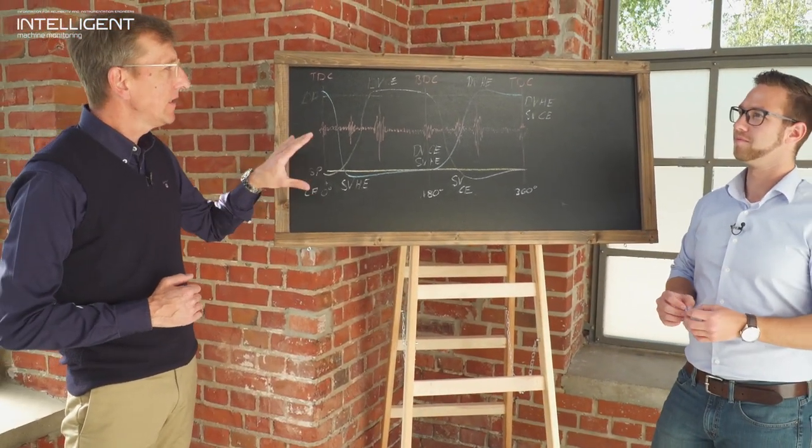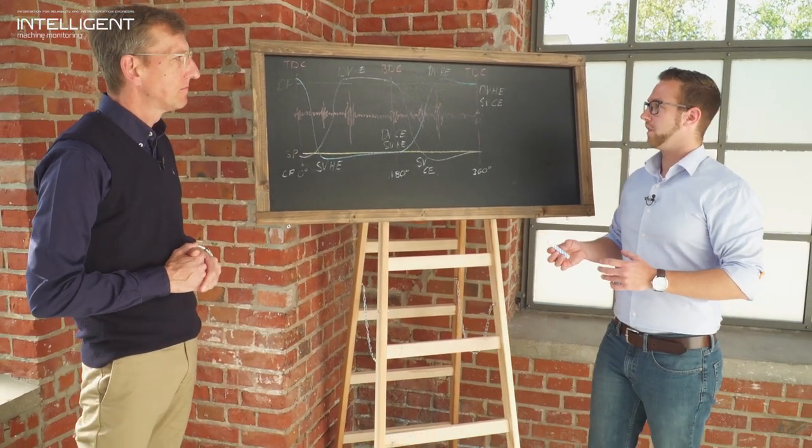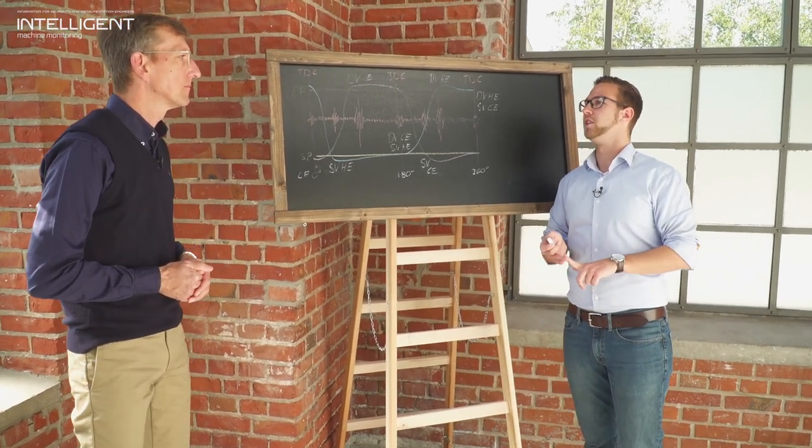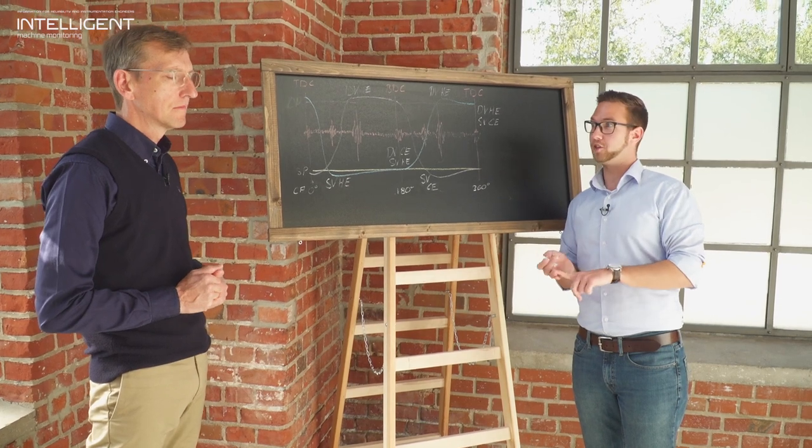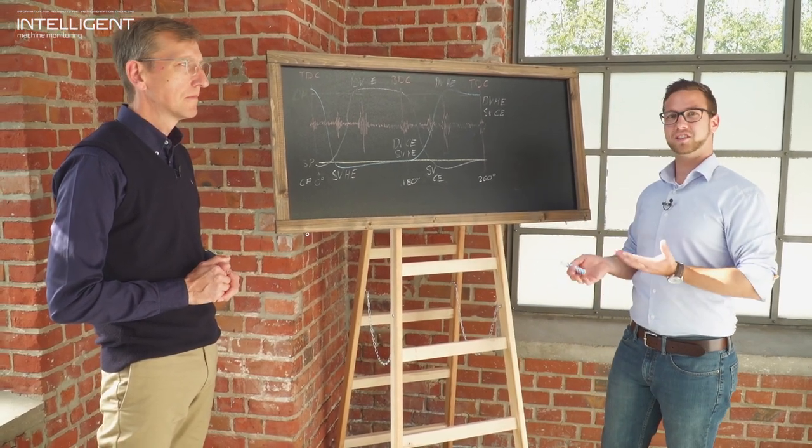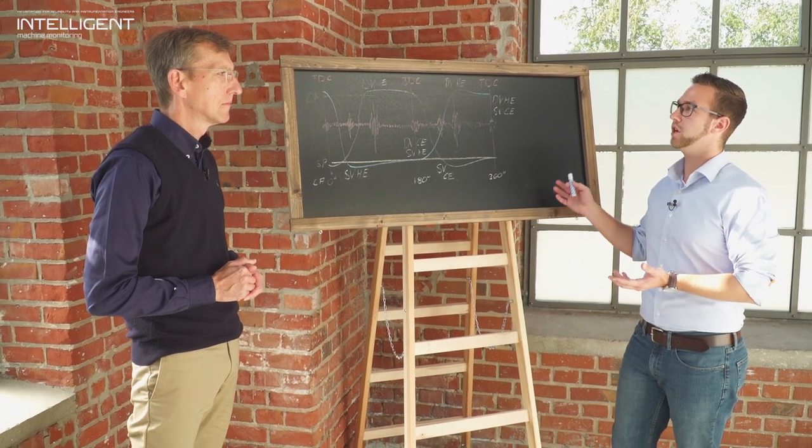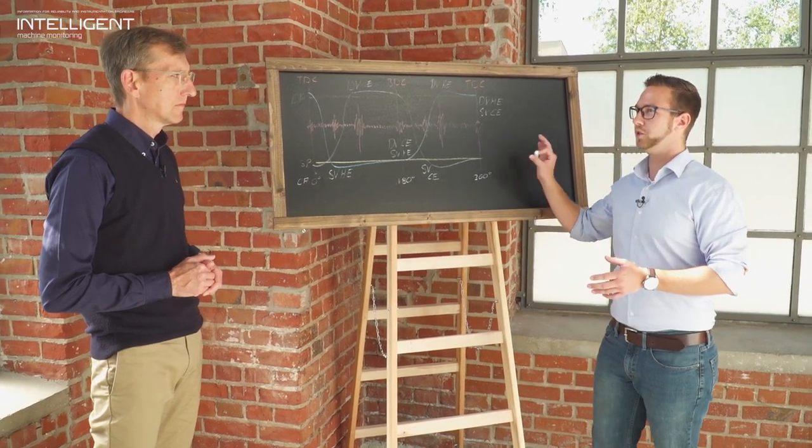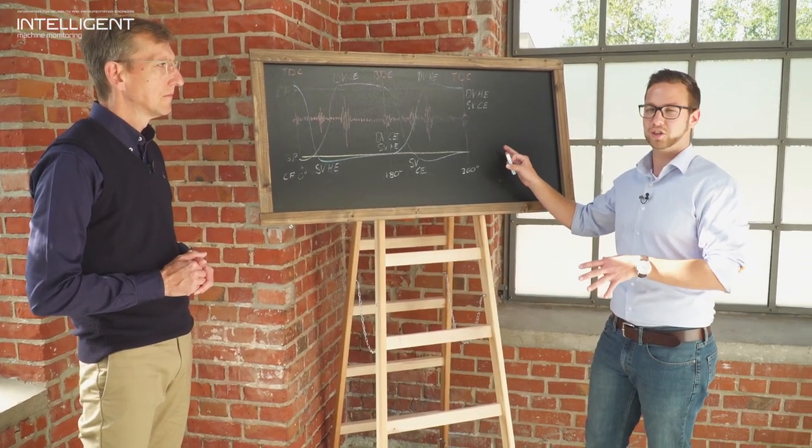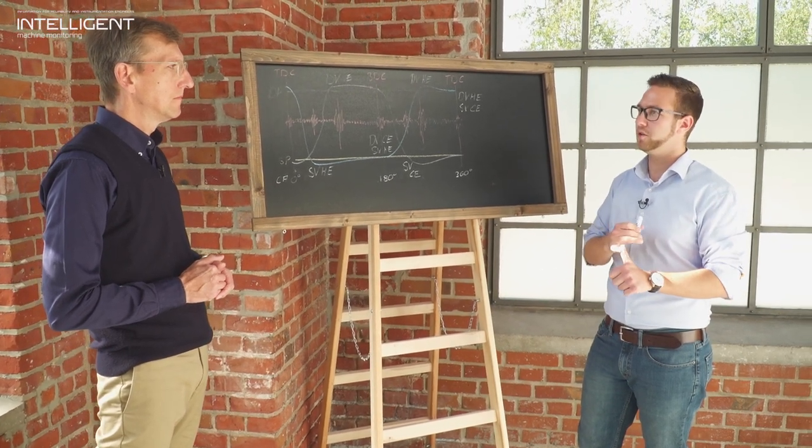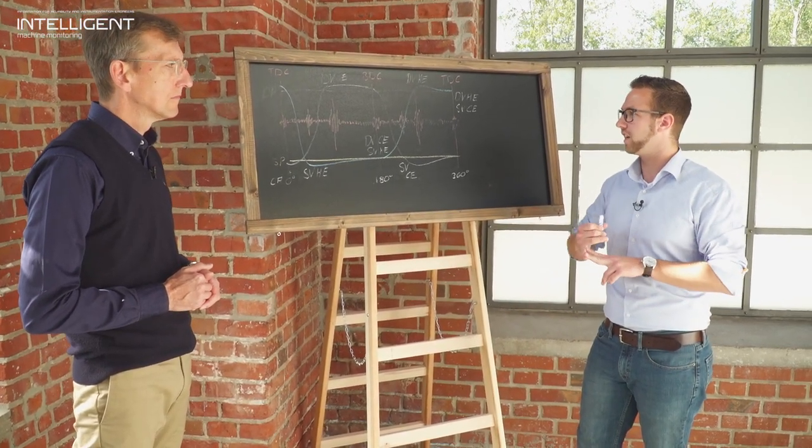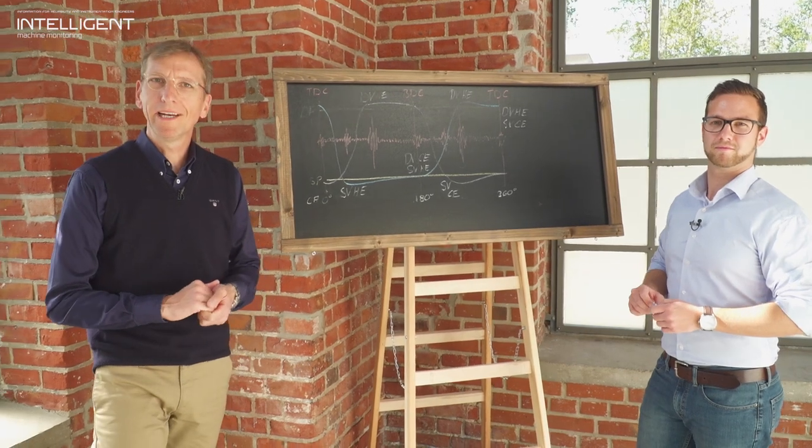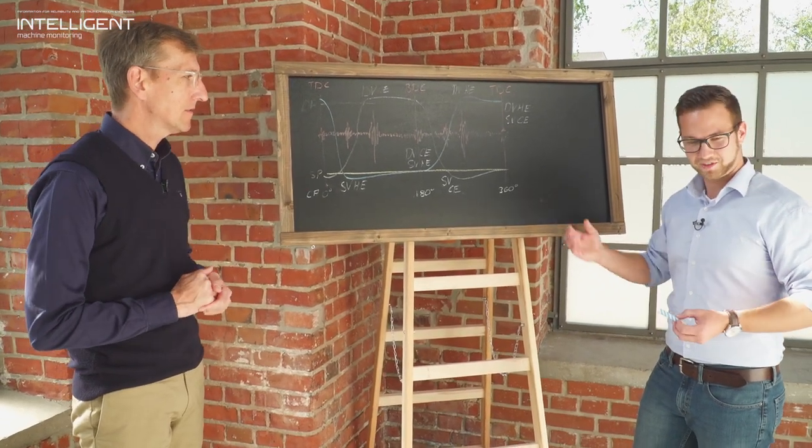For our audience, what is the key takeaway? The key takeaway is if you only use vibration or if you only use pressure analysis, you will have good indications for what's happening on your process and on your compressor, but you will never get the full clear picture. If you really want to know and if you want a fast analysis, which is usually the case if you're the operator, I would recommend to use both to get the full picture and compare what is happening. Never use only one signal. Use always more than one signal and everything you can get to make a full analysis. That sounds pretty comprehensive. Thank you for that Jonas.